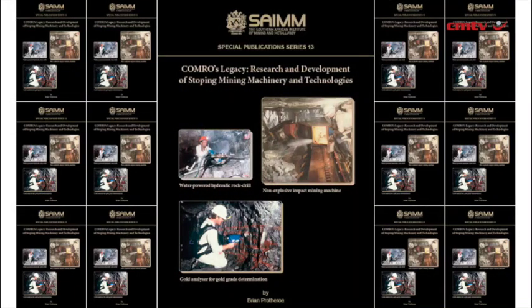And we looked at what was available, and the route followed was looking at developing a portable X-ray fluorescent instrument. So we produced four instruments, and they were tested in the laboratory in simulated mining conditions. And obviously this process took place over a long time, and the instruments were then tested in this environment, and issues like intrinsic safety and the radiation aspect needed addressing. Then they actually took extensive field evaluation.